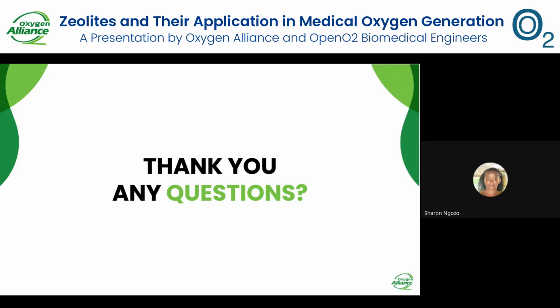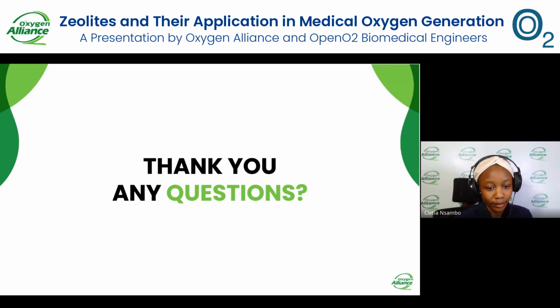Sharon? I have nothing to add. What you're saying might generally be true, but it may depend on how the concentrator was stored. In bad environments, where maybe there's dust or high humidity, I guess it might affect the zeolite. I hope that has answered that question.